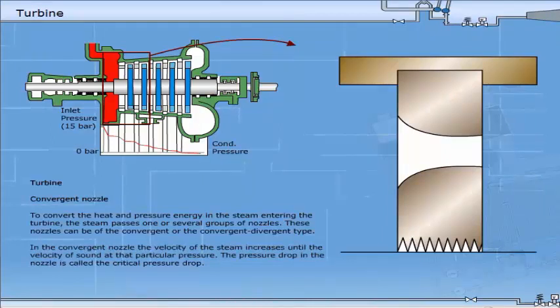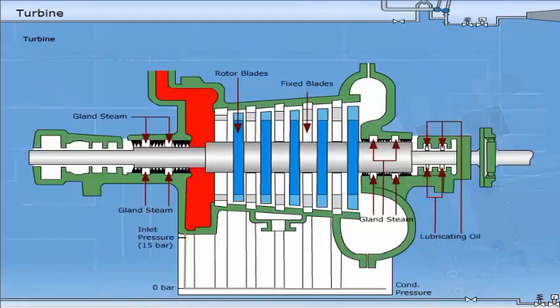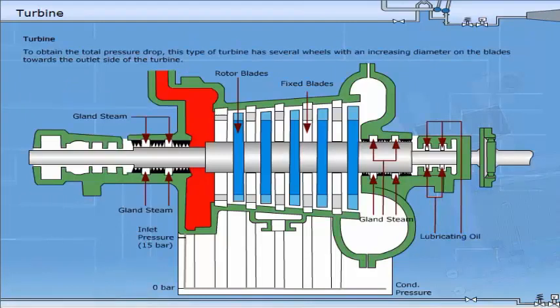The pressure drop in the nozzle is called the critical pressure drop. To obtain the total pressure drop, this type of turbine has several wheels with an increasing diameter on the blades towards the outlet side of the turbine.